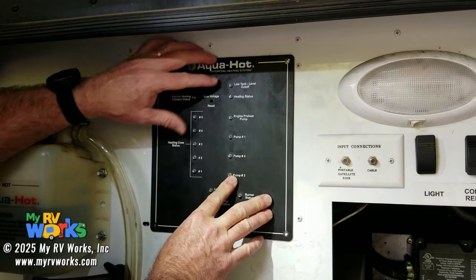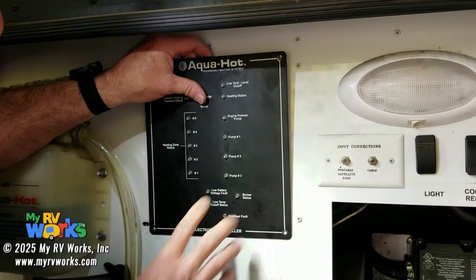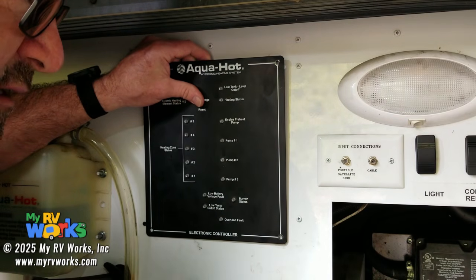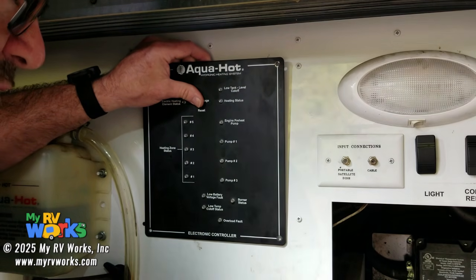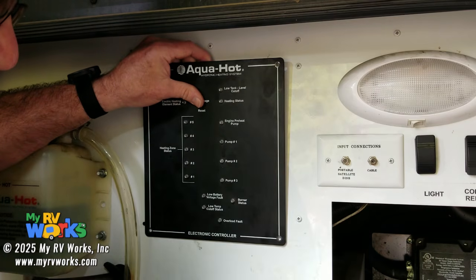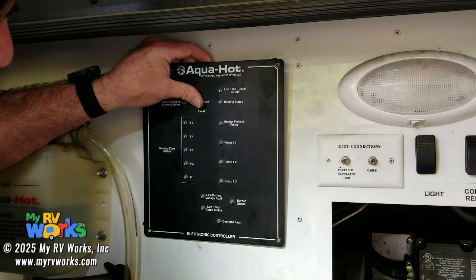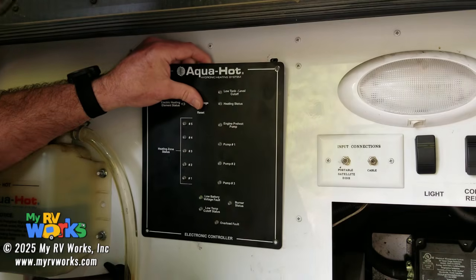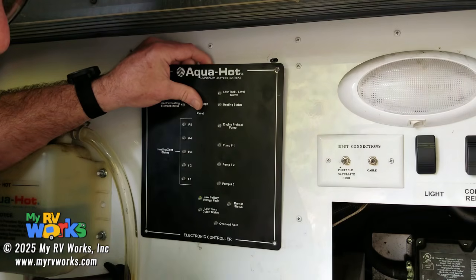If I have any red lights here, that means there's a problem, typically the pump has failed internally and you have to replace it. I've got a video on replacing pumps. You have to drain all your boiler antifreeze out, and if it's still new you can put it back in. Sometimes we also replace it, but it's up to the customer what they want to do since it's their unit.